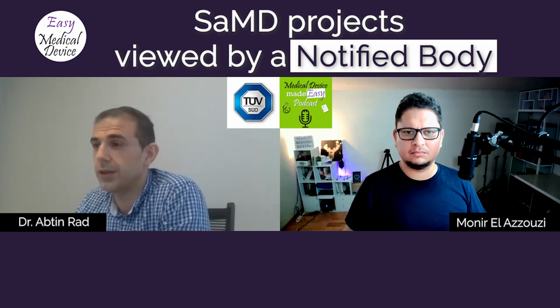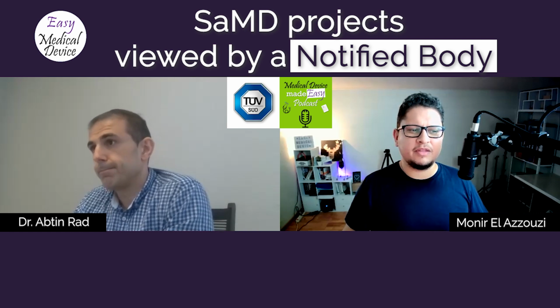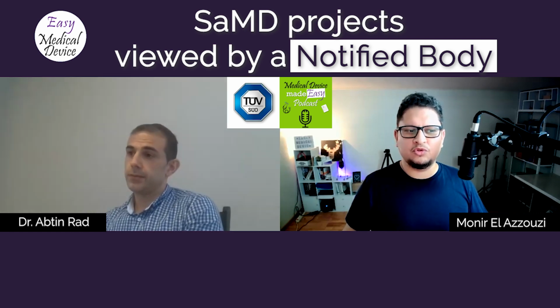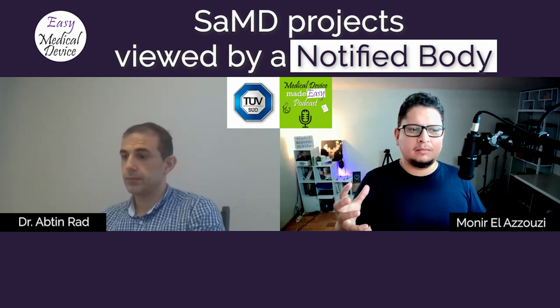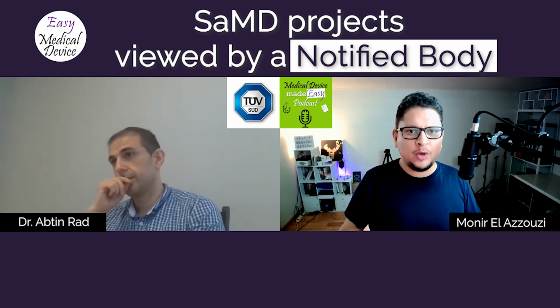So I have also had a discussion with some of my friends who work at BfArM, and they couldn't name me any example either, because we always end up with medical device or not a medical device. If it's a medical device, it somehow influences the therapy or diagnosis, so it does not fall in Class 1, and anything else is not a medical device if it does not influence the therapy or diagnosis. So this is, I think, important to inform people that 99% of your devices that are software are mainly Class 2A as a minimum.